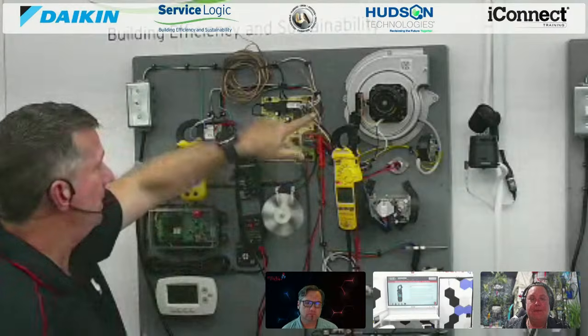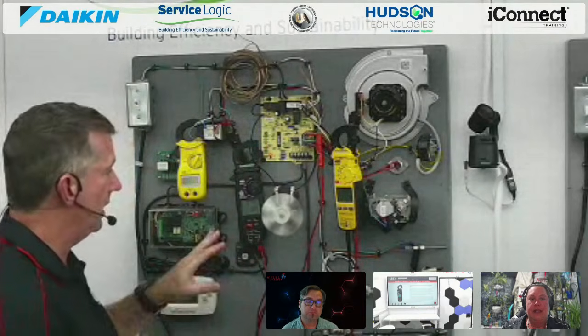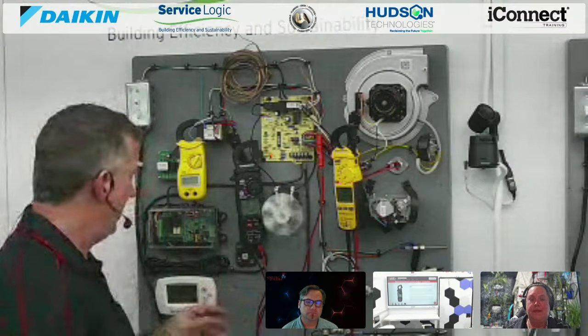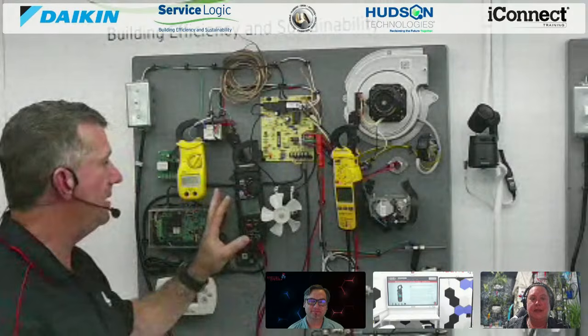But I don't have voltage applied on that wire like I was reading with standard voltage. So when we start troubleshooting wiring diagrams and equipment, and we think we're chasing partial voltages but can't figure out where they're coming from, it becomes important to understand: is that an actual voltage coming through, or an induced voltage I've been chasing improperly? Using that Low Z function really changes the way we become troubleshooters and service technicians. It will truly save you a lot of time.